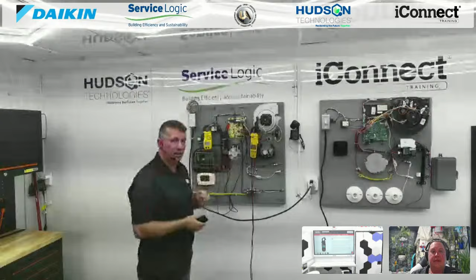I really like being able to do that. When we start looking at the efficiency of a system, we're going to see the day, maybe much sooner than most realize, when if you're doing a heat pump installation and looking for a rebate from a local utility, they're going to require a commissioning report. They want to know the efficiency of this, because if I add poor ductwork onto this thing and slow this motor down, we'll see.